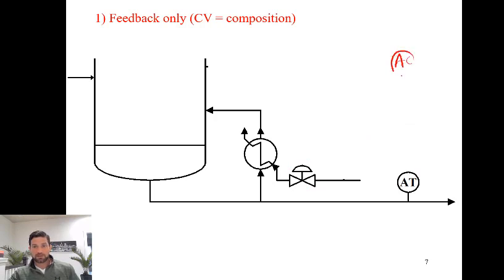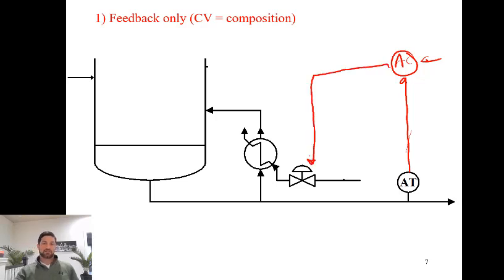So what we can do is draw a composition controller. Based on changes in the composition, it is going to tell the steam controller to increase or decrease the amount of heating to the reboiler, and that's going to affect the composition. So that would be the bottoms of the distillation column, without any sort of cascade control, feedback only. And I suppose I should say specified here.